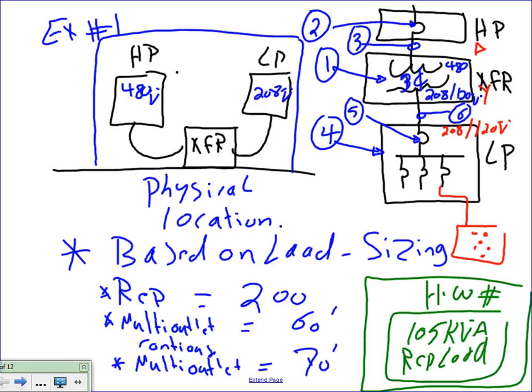After we size it, we need to size the overcurrent protection device that protects it and the feeder that feeds the transformer, which is this part here. Then we go to the secondary and size the secondary conductors, which at the same time are the feeder for the lighting panel, this part here. Then we find the overcurrent protection device for the panel and the panel size itself. That's very typical. From the low voltage panel, you're going to be feeding receptacles. That's the only reason we do this, to feed receptacles. Lights, we can burn at 277.